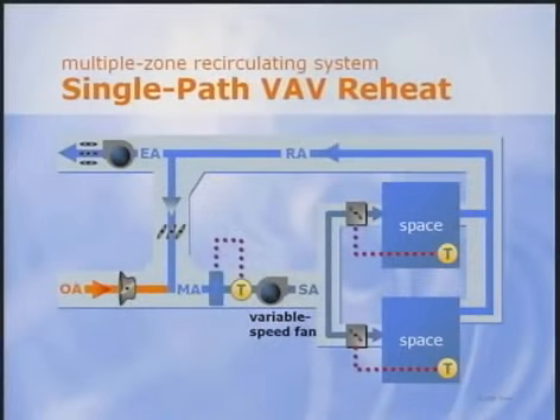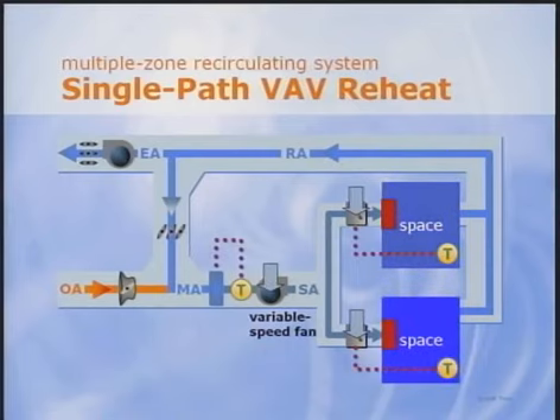Single-path VAV systems supply variable volume, constant temperature air to all zones. Primary airflow must drop as zone cooling load drops, but this air provides both cooling and ventilation, so it can only drop so far. Once primary airflow reaches some minimum value, any further reduction in zone cooling load results in subcooling. The only way to avoid subcooling is to add heat. So many perimeter VAV zones use reheat at the VAV box. In these zones, designers must determine the right minimum settings to maintain proper ventilation without using excessive reheat. But what's right? That's what we want to find out. But first, let's look at what Standard 62 requires.